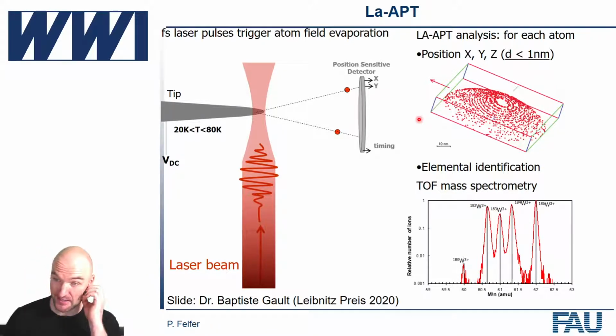The good thing in this case, though, is if you want to increase your temporal resolution, the time that it takes your sample to cool is constant. Unless you pulse very, very short, like every 5 nanoseconds or so, which is completely pointless because then we'd have 5 pulses before the atom even hits a detector. Just as a hint, typical flight times in atom probe are between 50 nanoseconds and 1 or 2 microseconds, depending on the flight path length and what element it is and what voltage and so on.